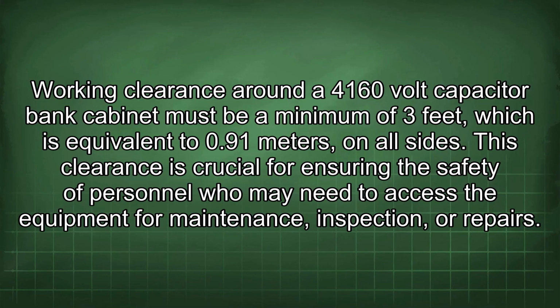Working clearance around a 4,160-volt capacitor bank cabinet must be a minimum of 3 feet, which is equivalent to 0.91 meters, on all sides.